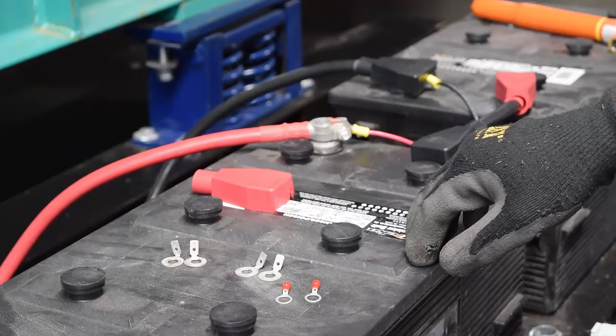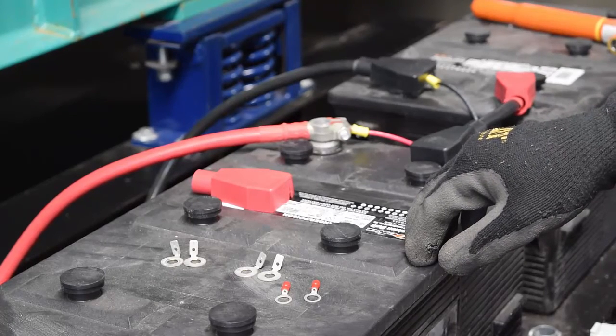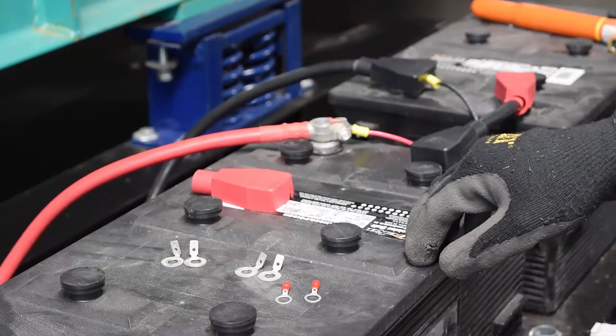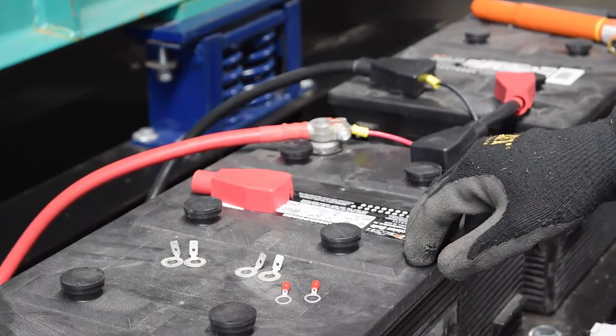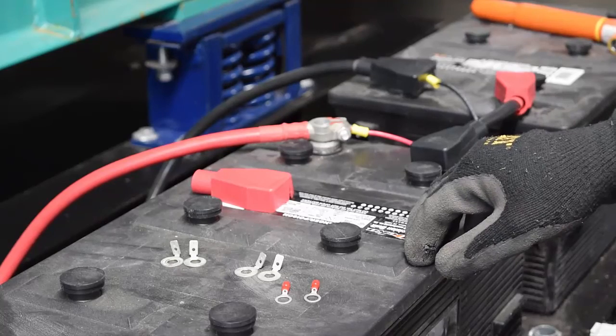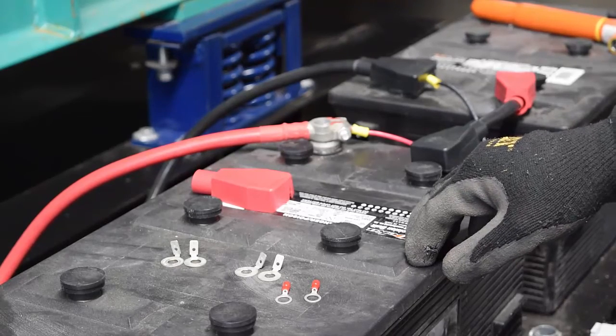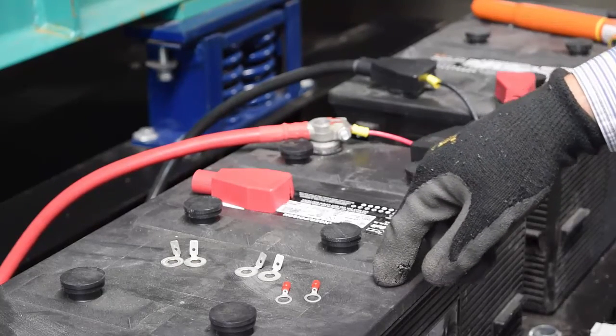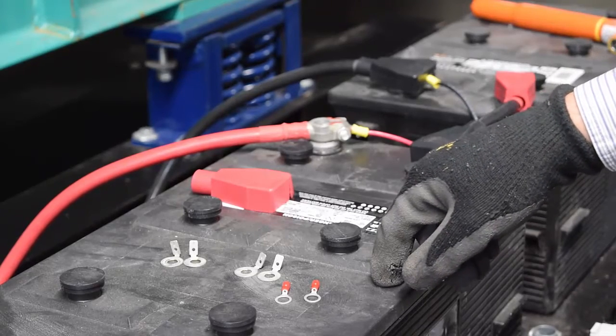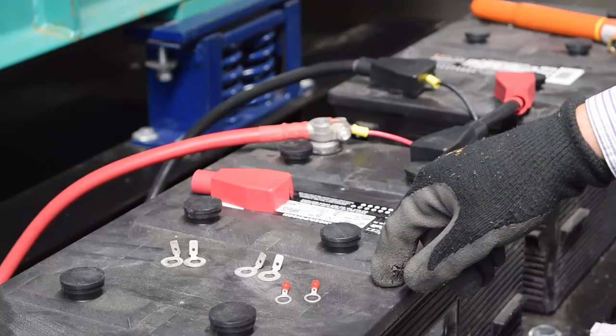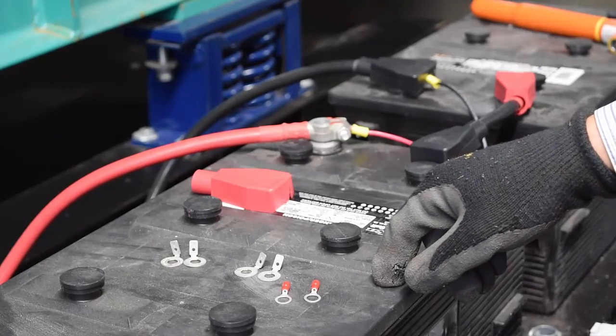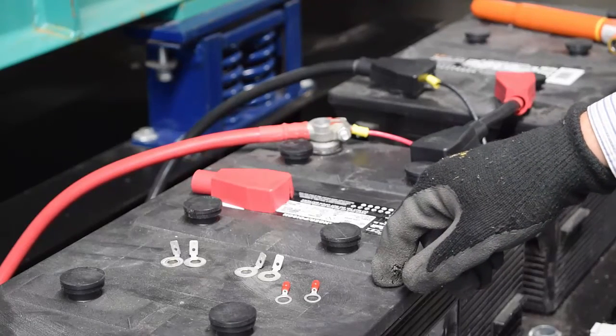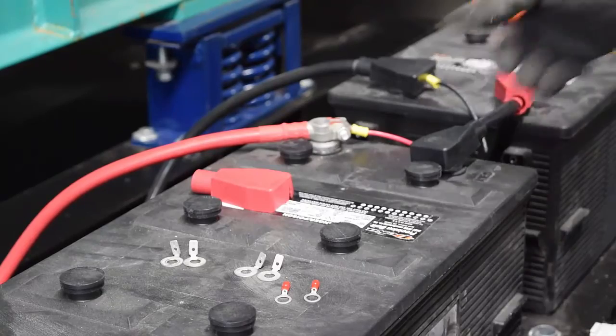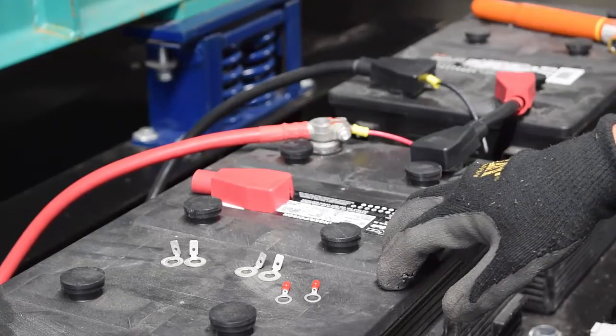And you can easily check if your CellQ1 is configured to use the AC-DC adapter or the battery string by checking the part number label on the controller. The last two characters in the part number indicate the input power. A4 uses the AC-DC adapter. D0 uses 12 volts DC from the battery string. D1 uses 24 volts DC from the battery string, like we have today. And D2 uses 48 volts DC from the battery string.